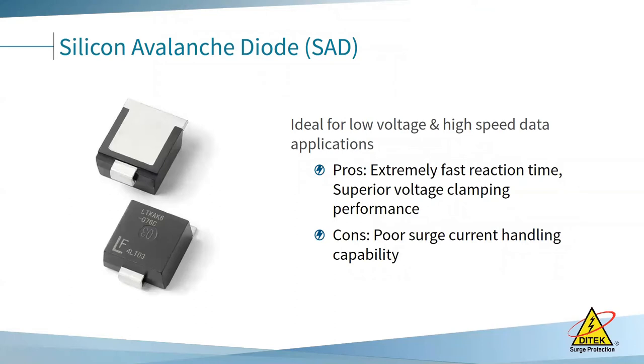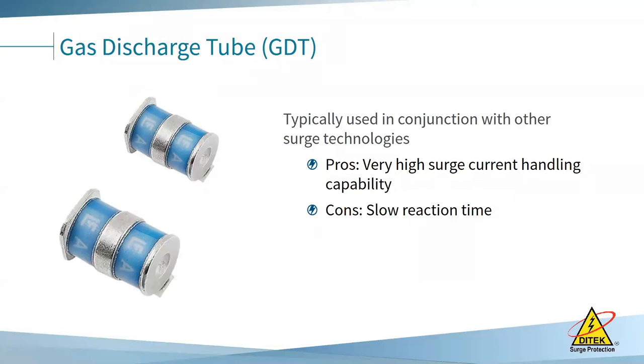Another component is the silicon avalanche diode (SAD). These are ideal in low voltage and high-speed data applications — they react very quickly and have superior voltage clamping performance. However, they don't have high surge current handling. So they are often coupled with gas discharge tubes (GDTs), which have a slow reaction time but high surge current handling capability. When you combine SADs with GDTs, you've got the best of both worlds.